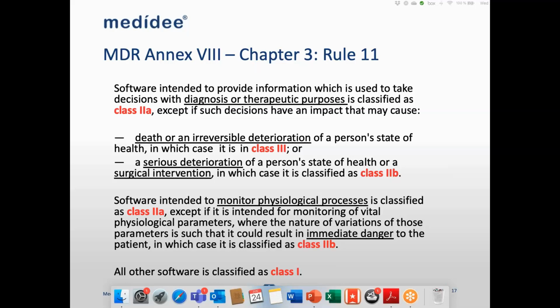So in a generic sense, one of the primary reasons for incorporating rule number 11 within the MDR is the fact that in most cases medical device software does not directly relate to risks, rather it only relates to the consequences of indirect harm or failure to provide the correct information. So if a software is failing to provide the correct information, in the majority of cases medical device software is related indirectly to the harm or the failure.